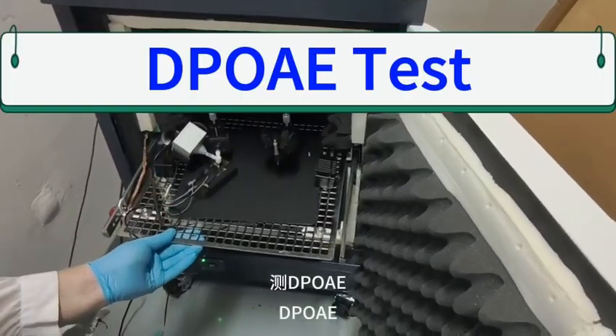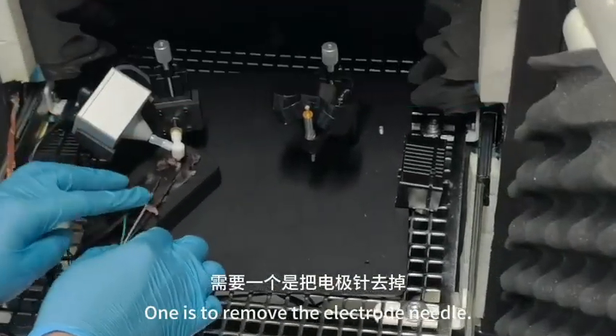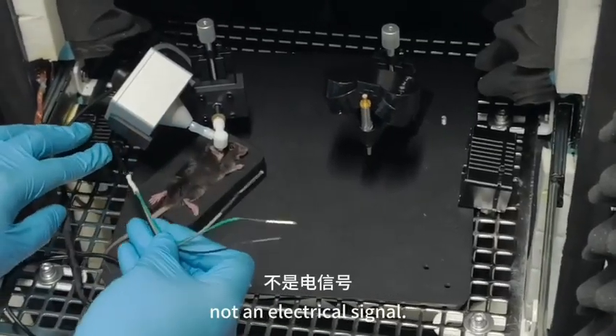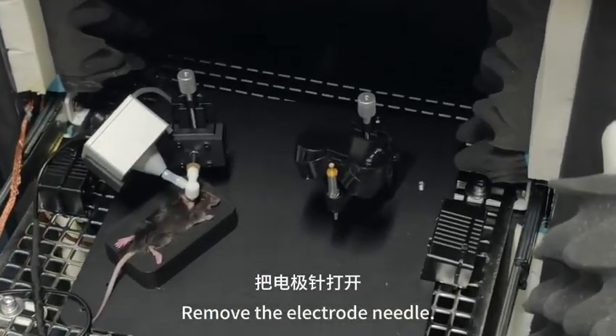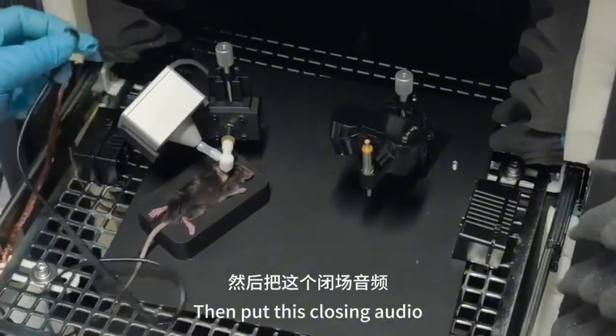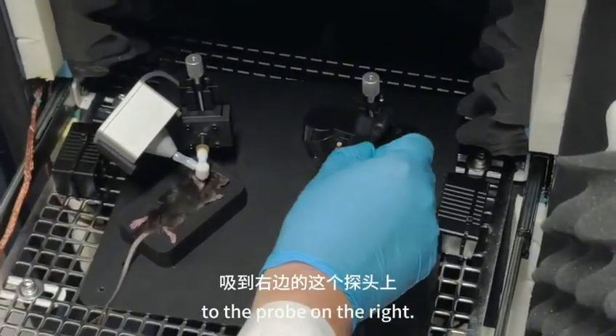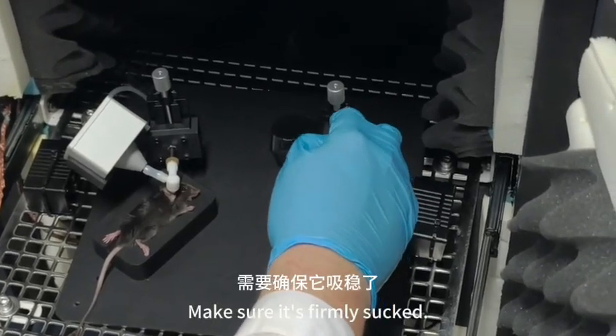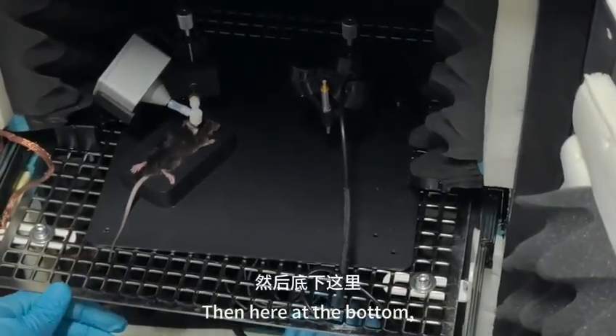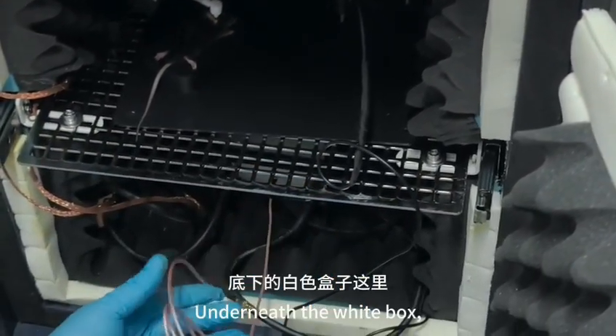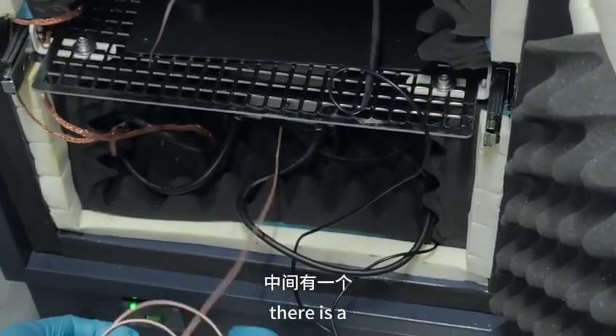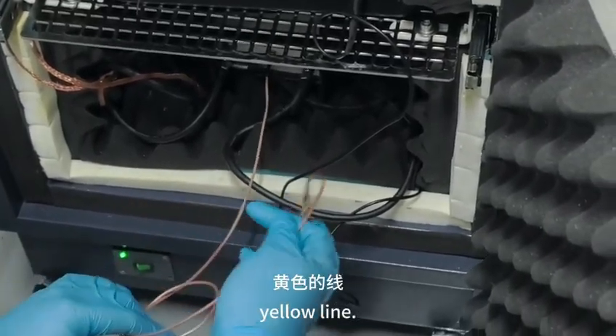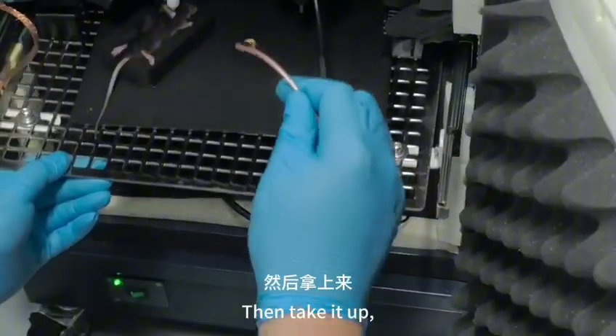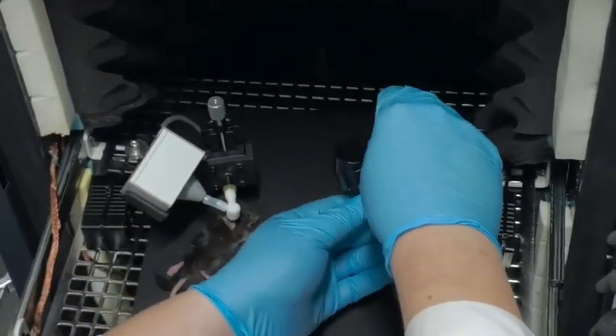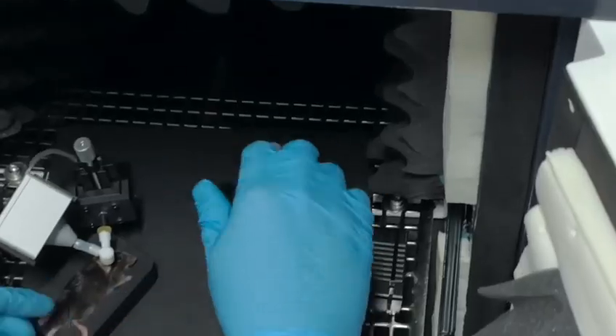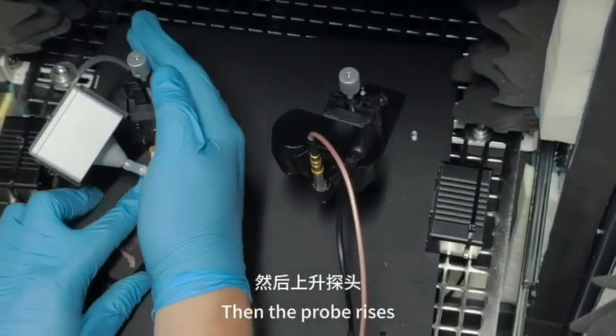To measure DPOAE, first remove the electrode needle. DPOAE collects sound signals, not an electric signal. Remove the electrode needle. Then suck the closed field audio to the probe on the right. Make sure it's firmly sucked. Then, at the bottom, the white box below, there is a yellow line. Take it up and insert it into the probes, the microphone in the middle. Then raise the probe here.